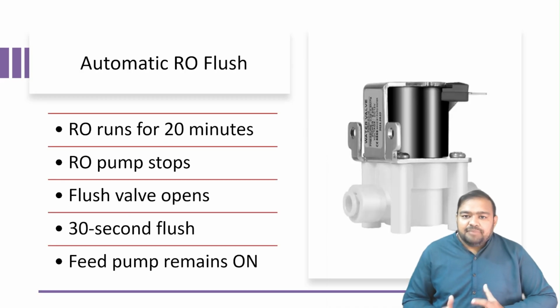To maintain membrane performance, an automatic flushing sequence is implemented. The logic is: the RO pump runs for 20 minutes. After 20 minutes, the RO pump stops. The flush solenoid valve opens. Flushing continues for 30 seconds. The feed pump continues running. After flushing, the RO pump restarts automatically. This sequence will require multiple timers and interlocks.